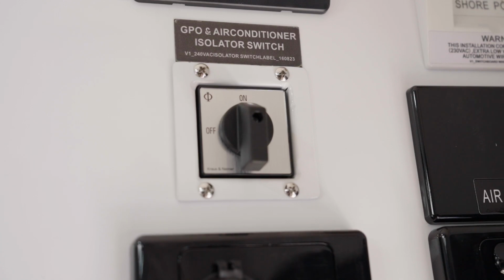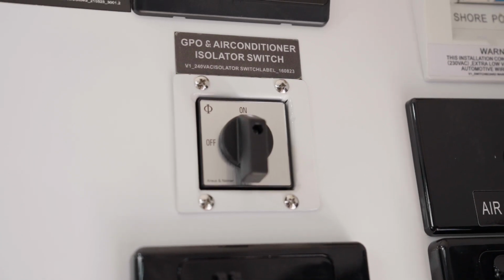And right here is a very handy 240 volt isolation switch. It will cut all 240 volt power to the whole system, cutting the connection between the external 240 volt inlet and everything else. MDC recommends keeping this in the on position unless you are servicing the 240 volt system and need to safely work on the mains connections.